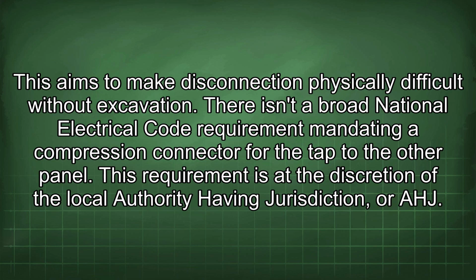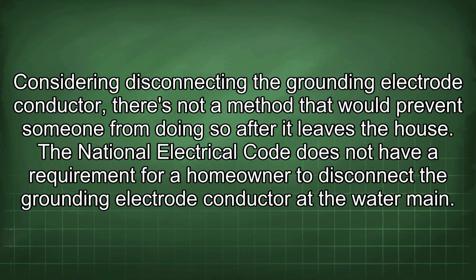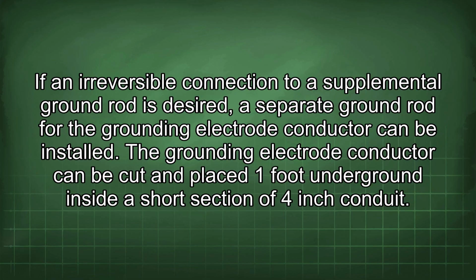There isn't a broad national electrical code requirement mandating a compression connector for the tap to the other panel. This requirement is at the discretion of the local authority having jurisdiction, or AHJ. Considering disconnecting the grounding electrode conductor, there's not a method that would prevent someone from doing so after it leaves the house. The National Electrical Code does not have a requirement for a homeowner to disconnect the grounding electrode conductor at the water main. If an irreversible connection to a supplemental ground rod is desired, a separate ground rod for the grounding electrode conductor can be installed.